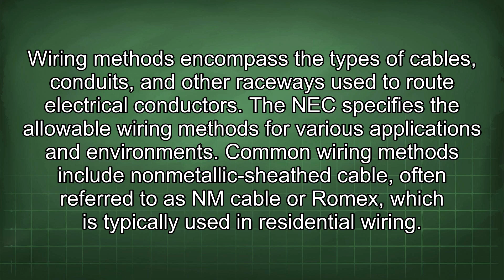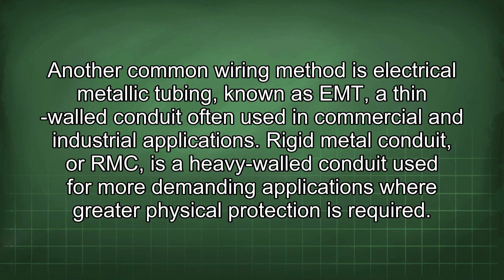Common wiring methods include non-metallic sheathed cable, often referred to as NM cable or Romex, which is typically used in residential wiring. Another common wiring method is electrical metallic tubing, known as EMT, a thin-walled conduit often used in commercial and industrial applications. Rigid metal conduit, or RMC, is a heavy-walled conduit used for more demanding applications where greater physical protection is required. Liquid-tight flexible metal conduit, known as LFMC, is a flexible conduit used in wet or damp locations. Cable trays are used to support and route cables in industrial and commercial buildings.